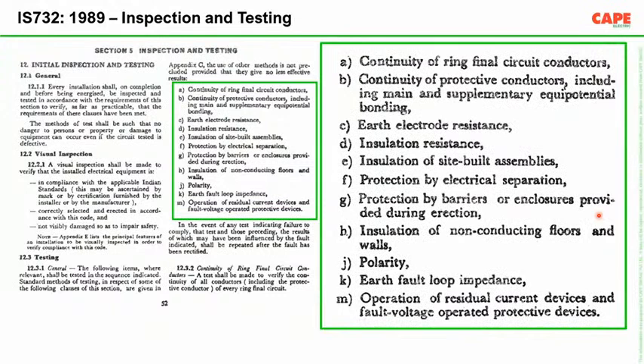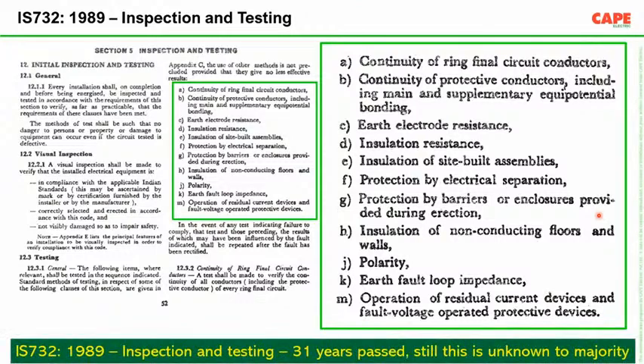And now what is written in 1989, inspection and testing, there are the tests which I have shown in the IEC standard. It was written 31 years back in India, but even today nobody follows this. As I said, I am yet to see a building which is tested as per IS 732. 31 years past, this standard is published, and now the most important point: in an installation tested as per this particular standard, not the new one, the 1989 standard, 90% of ignition of fire from electricity can be avoided.